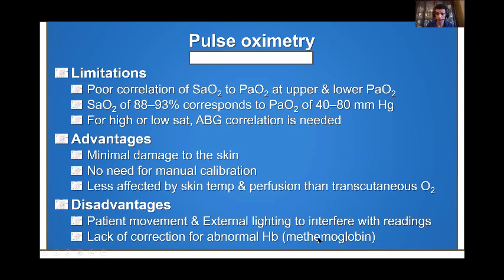The advantage of pulse oximetry is that because it measures light, it does not cause skin irritation and does not need frequent calibration. It is less affected by skin temperature or perfusion changes. The disadvantage is that it has a lot of artifacts when patients move or when there is ambient light. Also, it does not measure abnormal hemoglobin types such as methemoglobin or carboxyhemoglobin. If you need to measure methemoglobin, use a blood gas or co-pulse oximetry instead.